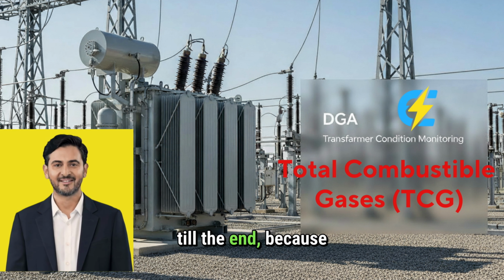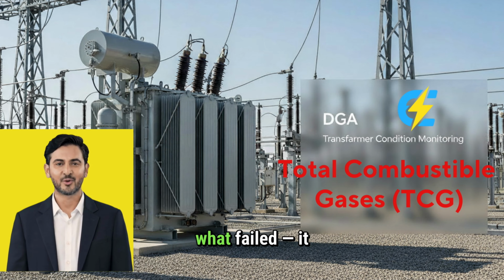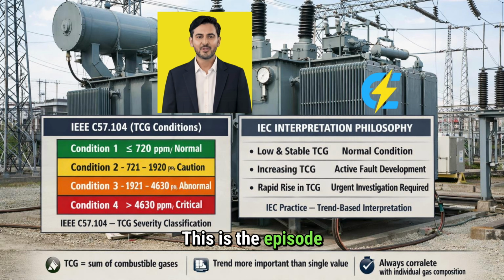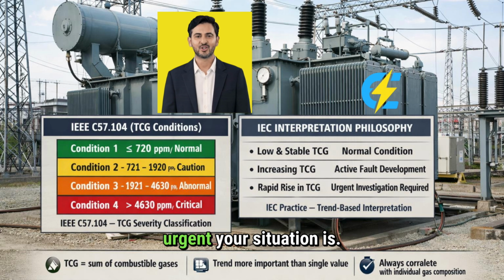Stay till the end. Because TCG doesn't tell you what failed. It tells you how serious the situation is. This is the episode where engineers stop analyzing individual gases and start making decisions. When you've been working with transformer dissolved gas analysis for years, you reach a point where the complexity of individual gas interpretation gives way to something more powerful. A single number that tells you exactly how urgent your situation is. That number is total combustible gases, or TCG.